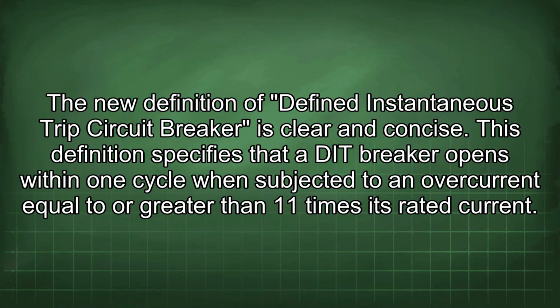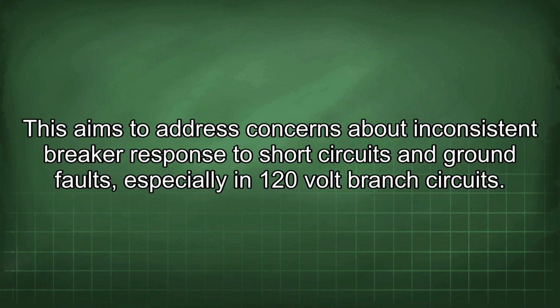The new definition of defined instantaneous trip circuit breaker is clear and concise. This definition specifies that a DIT breaker opens within one cycle when subjected to an overcurrent equal to or greater than 11 times its rated current. This aims to address concerns about inconsistent breaker response to short circuits and ground faults, especially in 120-volt branch circuits.